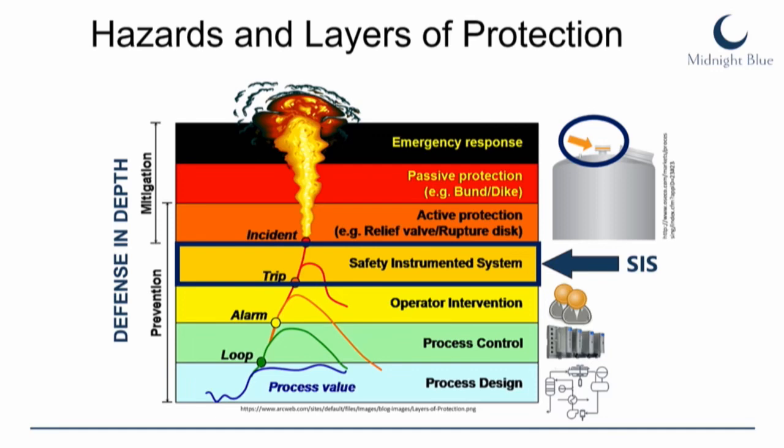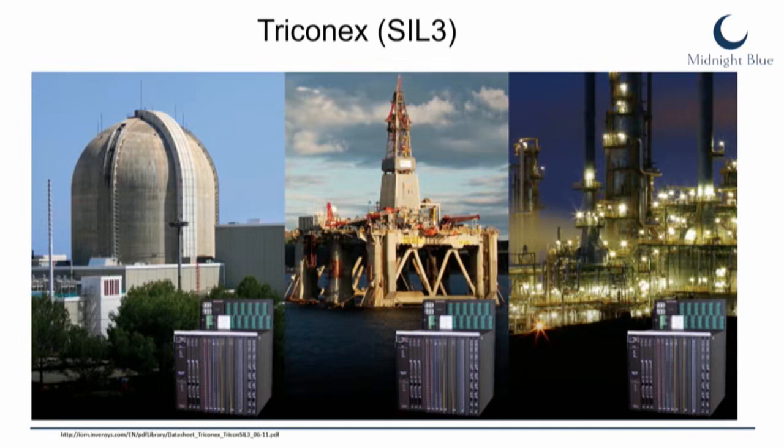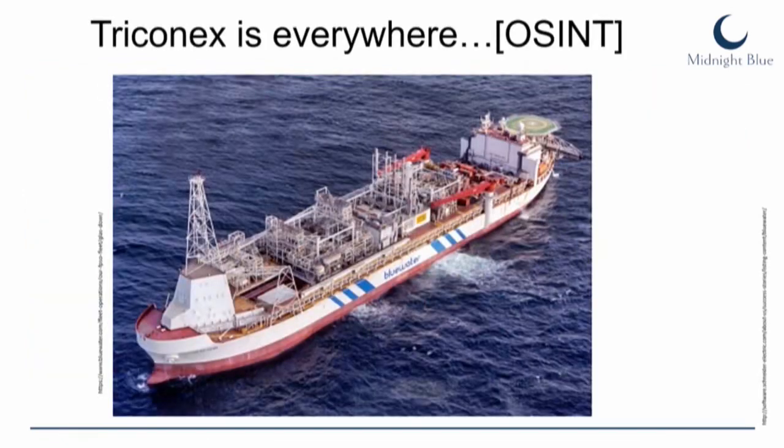The layers of protection start with the design of the process, then control loops, then a human operator who reacts to alarms. But as soon as the control system and human operator can no longer control the process safely, we have a safety instrumented system — an independent control system that reacts to hazardous conditions and tries to prevent them. This is the last line of defense before a hazardous accident occurs. The attacker was apparently trying to disable this system, which is effectively an attack on civilians. The targeted device was the Triconex from Schneider — a safety integrity level three system, found in over 18,000 installations across more than 80 countries.